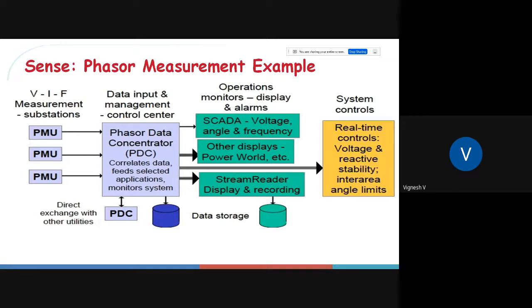So PMU gives us voltage, current, frequency information that goes to the PDC. From the PDC, we also have the SCADA value and other displays. And we have the system controls, which make real-time control decisions like voltage stability, reactive power support, interarea angles, limits on transmission lines, and things like that. So when you have both PMU and SCADA data, you would have a kind of hybrid system, but only with the PMU data, the advantage is that it has a very high refresh rate.